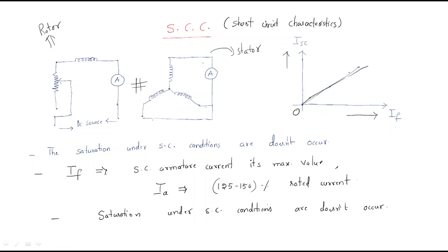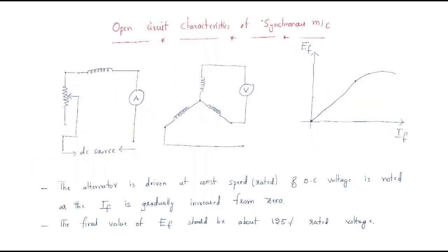Next are the open circuit characteristics of the synchronous machine. Here, all armature terminals are opened and a voltmeter is connected across any two phases or between line terminals. The rotor field is excited with a DC source, and an ammeter is connected in the field circuit.